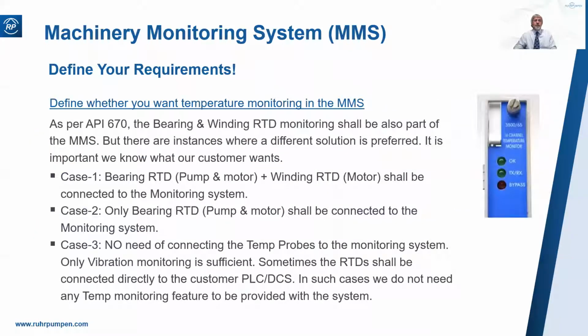Now, you also need to tell us whether you want temperature monitoring in the MMS. It's quite common for people only to want the vibration monitoring in the MMS, and the temperature signals get sent to the customer PLC or DCS. But sometimes you'll want them in the MMS. So tell us.